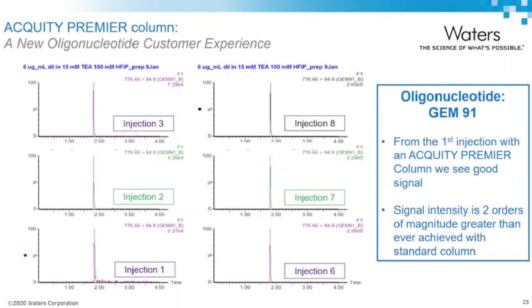It is because only the column is now treated with high-performance surfaces, but the LC system still has some metallic parts that are untreated. And even when conditioned, you may still see some partial loss of analyte. If you want to know more about how we can handle this situation, please contact Waters specialists. Due to time constraints, I'm not going to talk about it now.